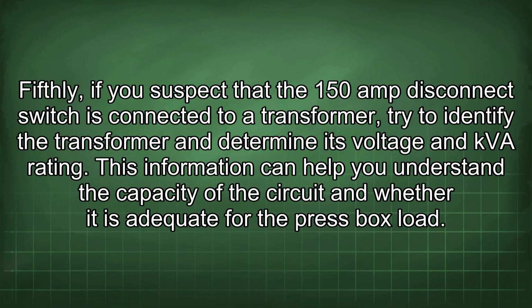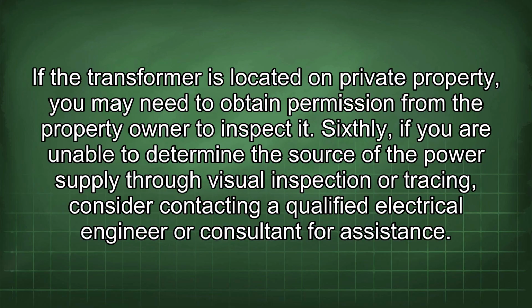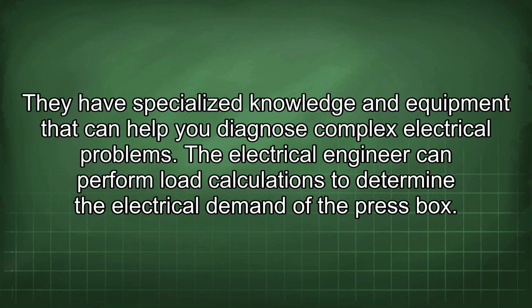Fifthly, if you suspect that the 150 amp disconnect switch is connected to a transformer, try to identify the transformer and determine its voltage and kVA rating. This information can help you understand the capacity of the circuit and whether it is adequate for the press box load. If the transformer is located on private property, you may need to obtain permission from the property owner to inspect it. Sixthly, if you are unable to determine the source of the power supply through visual inspection or tracing, consider contacting a qualified electrical engineer or consultant for assistance. They have specialized knowledge and equipment that can help you diagnose complex electrical problems.